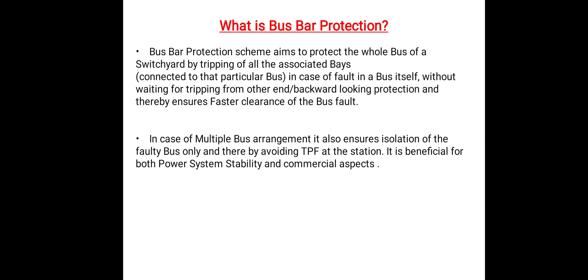Bus bar protection scheme aims to protect the whole bus of switch yard by tripping off all associated bays in case of fault in a bus itself, without waiting for tripping from other end backward-looking protection, and thereby ensure faster clearance of the bus fault. Bus bar protection basically needs some special type of attention because of some different reasons.